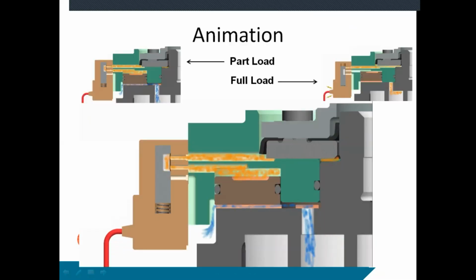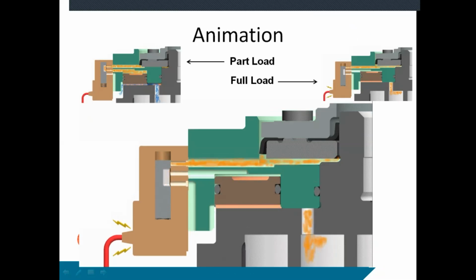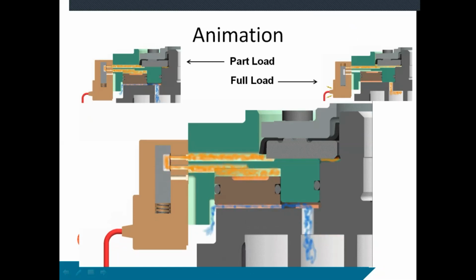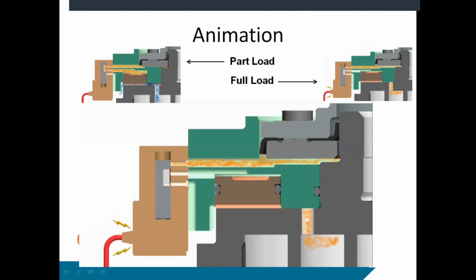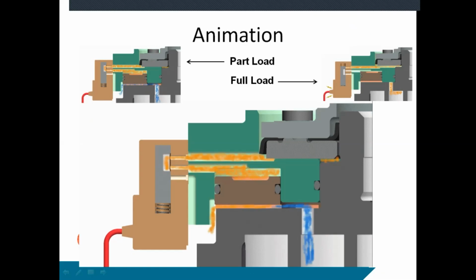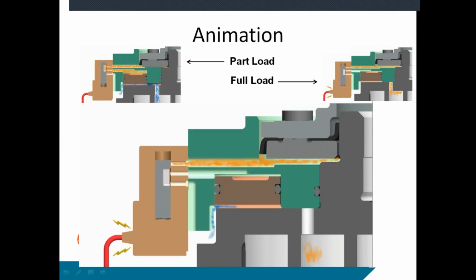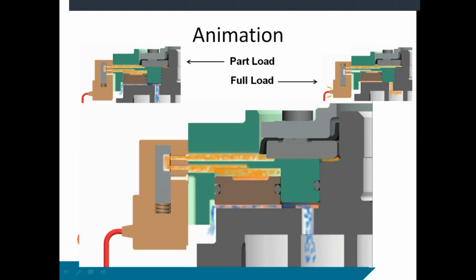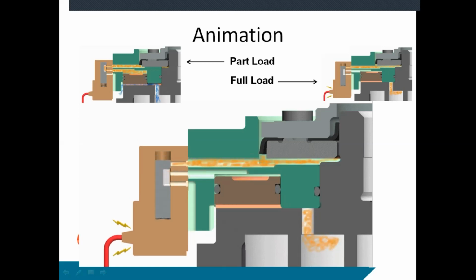When it's in part load operation, it bypasses back into the shell. And when it's in full load operation, it pumps 100% out. So this is basically showing you bypass and full load. It's just a three-way valve here that moves back and forth and diverts the gas. And that's how the new two-step scroll is going to operate as they come out. It shouldn't change the noise, the sound, or the amp draw. It shouldn't change any of that.